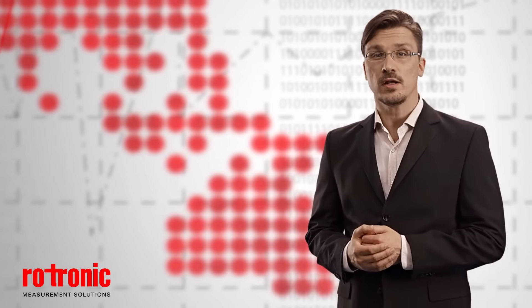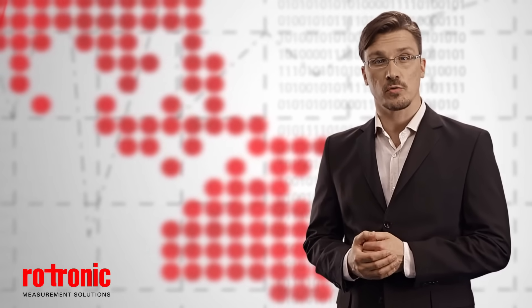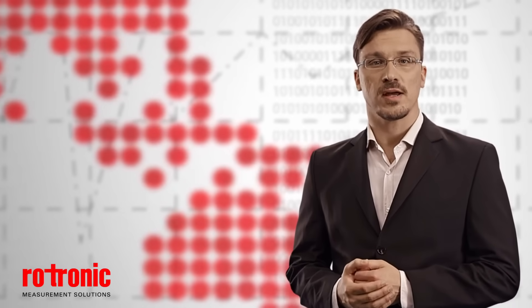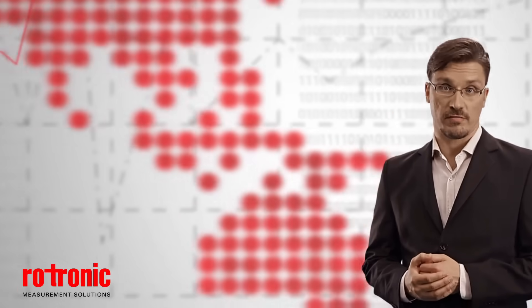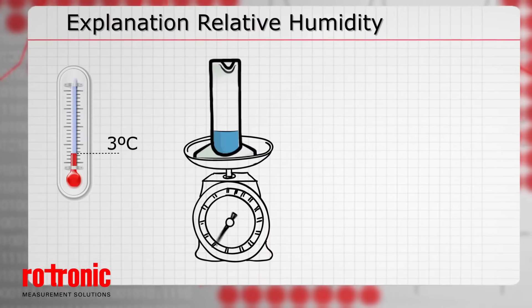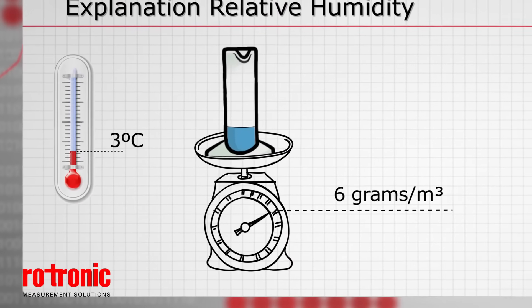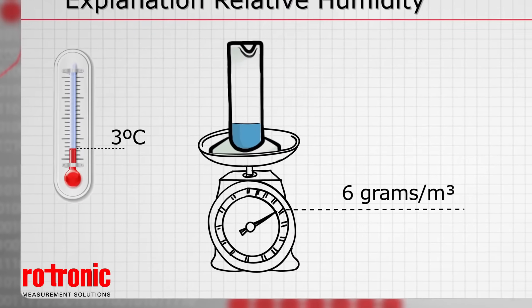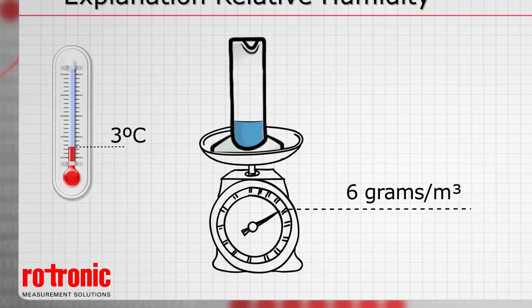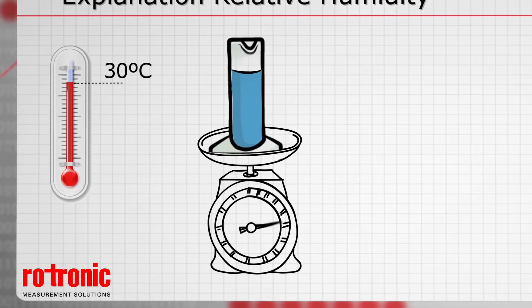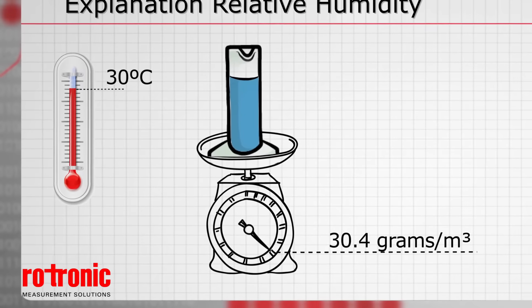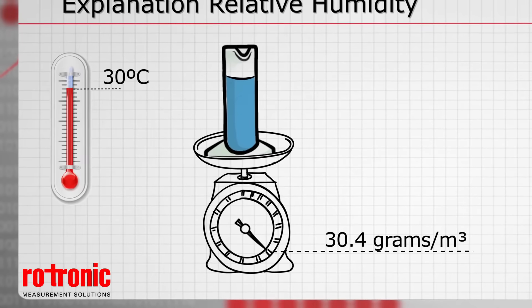Air can only absorb a certain amount of water vapor. This amount depends on the temperature of the air. At an air temperature of 3 degrees Celsius, this amount is a maximum of 6 grams of water vapor per cubic meter. The amount at 30 degrees Celsius is much higher, at 30.4 grams.